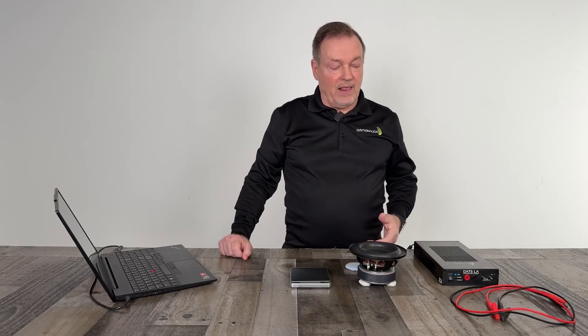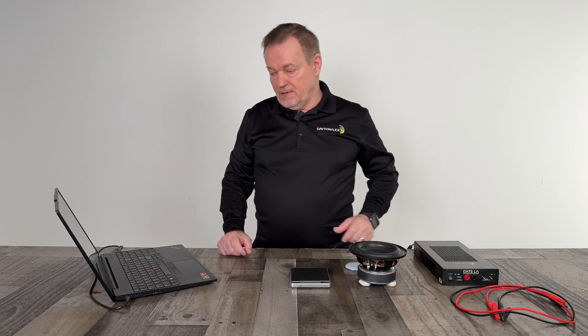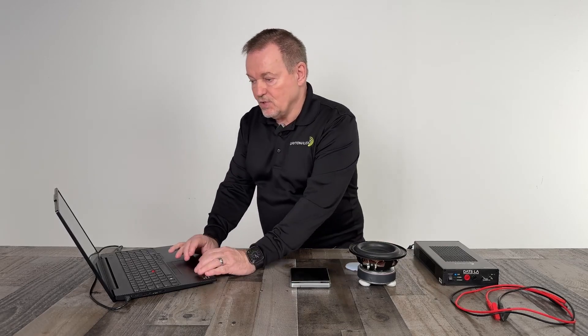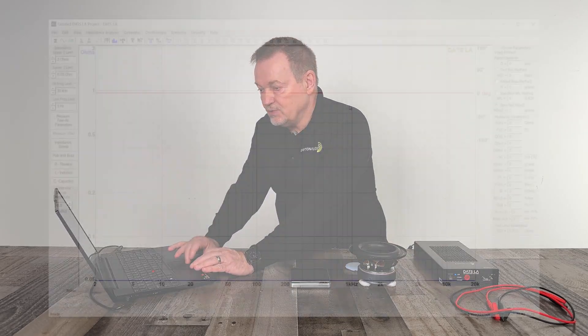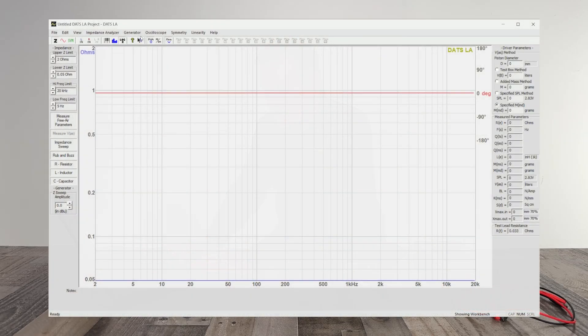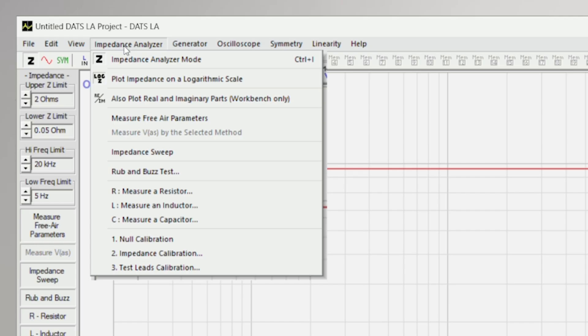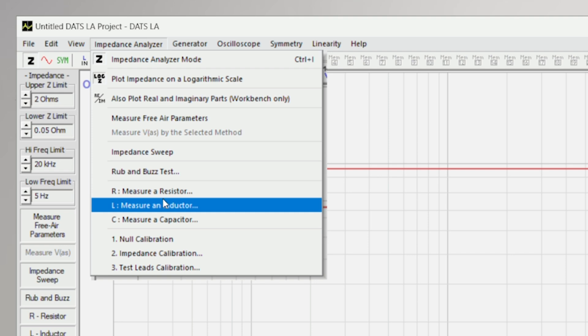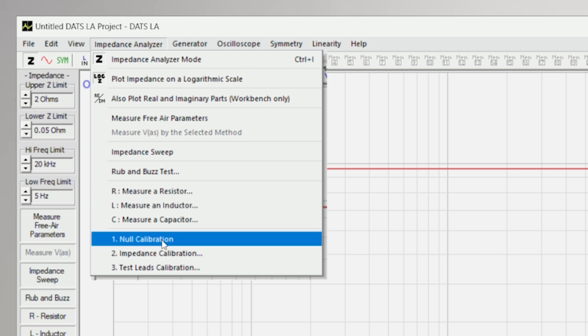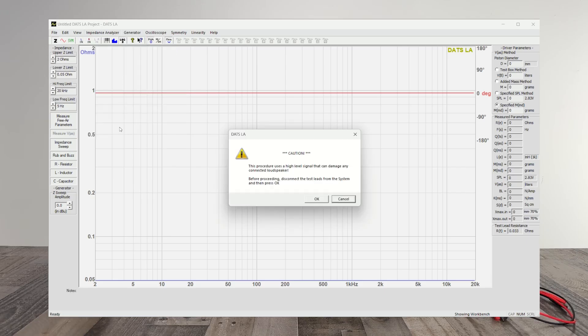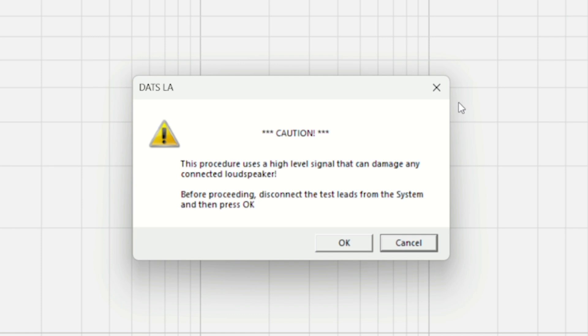To begin, we need to calibrate the device. So what we do, we go to the impedance analyzer. We're going through this calibration in the order that it's on the dropdown. So we do the null calibration.